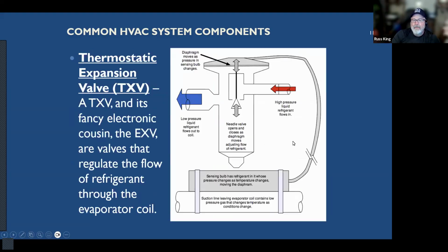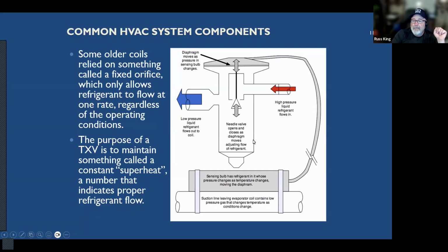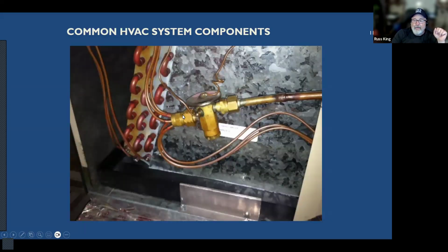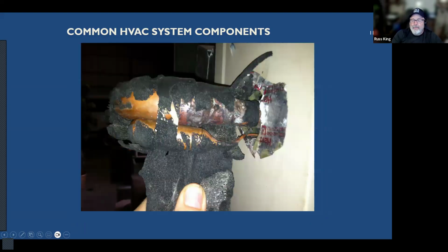Okay. There's a little thing called a TXV. I won't get into the TXV. It's pretty technical, but what a TXV does is allow the flow of refrigerant to adjust based on temperature changes. So as the temperature changes, it causes this little needle valve to open and close, and that changes the flow of refrigerant to kind of optimize it. That's how we squeeze a lot of extra efficiency out of air conditioners, with these TXVs. Okay. There's what a little TXV looks like. Okay. This is the sensing bulb for a TXV. This is very important to raters. They have to be able to check this.